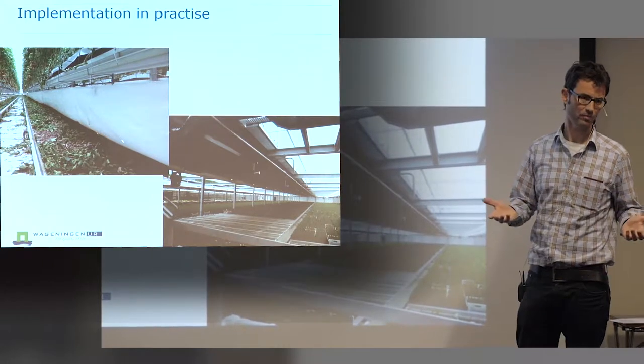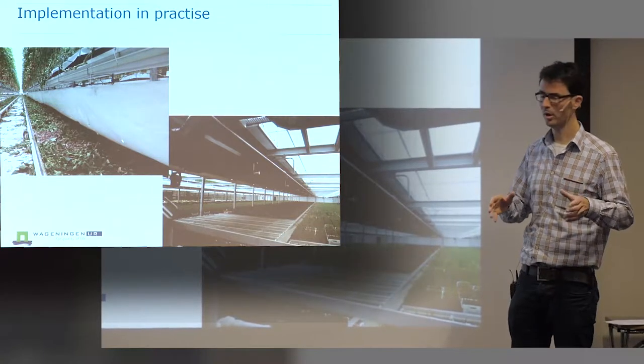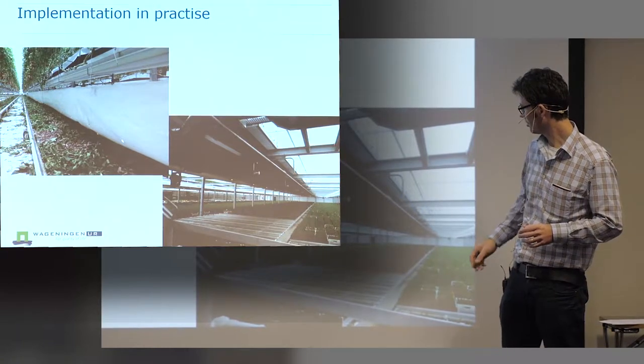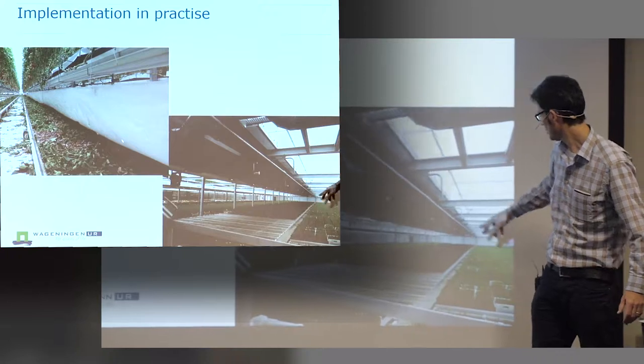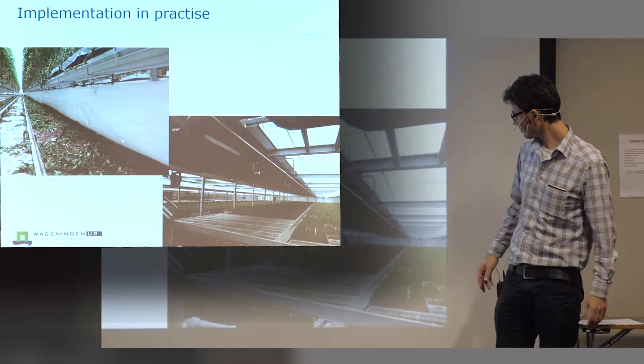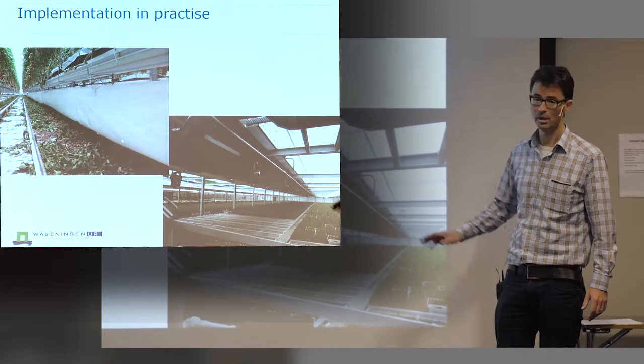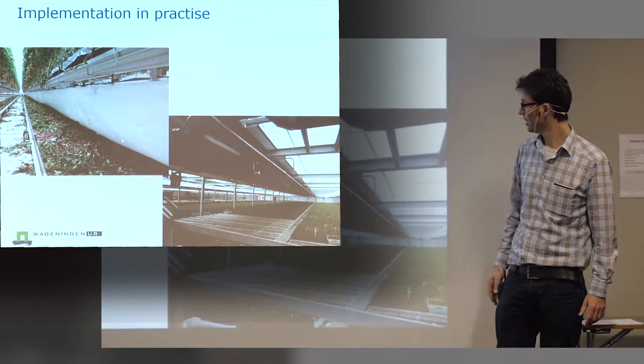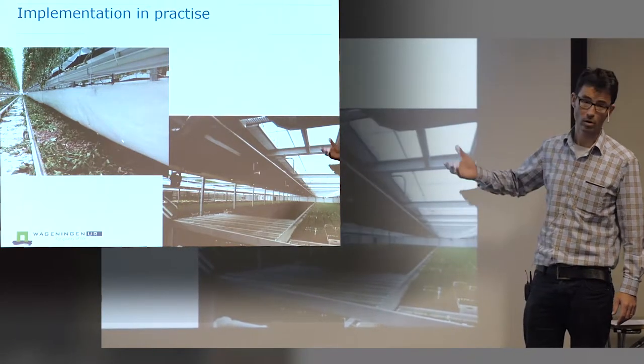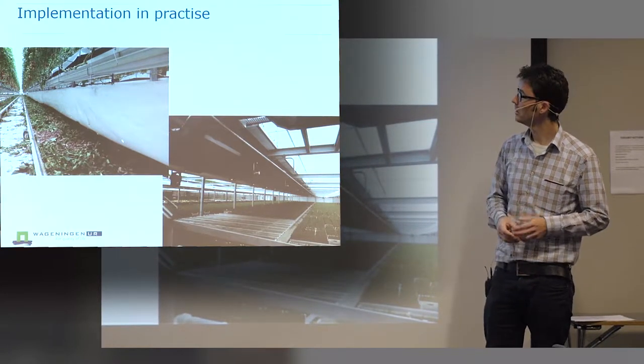And they also had a lot of issues with humidity, because for tulips, the humidity should remain below 70%, otherwise you get some strange defects in the tulip growing. So now they apply also these air ducts. You can see them here, and also in the tables below. It's a fully automated system, and that's also working very well, and they are very satisfied, because humidity was always a very big issue in tulip growing, and now with this system it's not anymore. So more and more growers are implementing this system, and I think all new greenhouses will be equipped with a system like this.